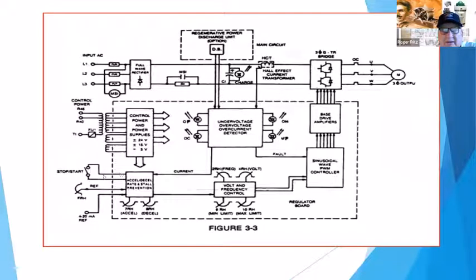Everything was done with a regular contact switch, a potentiometer out here, our 4 to 20 milliamp signals. You had to set your acceleration, deceleration, your upper limit, your lower limit, your high voltage, your lower voltage, your frequency that you're aspiring to. So all of that, you're basically just controlling the regulator board.